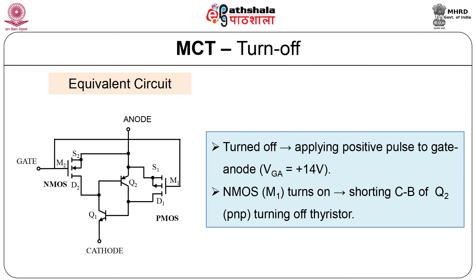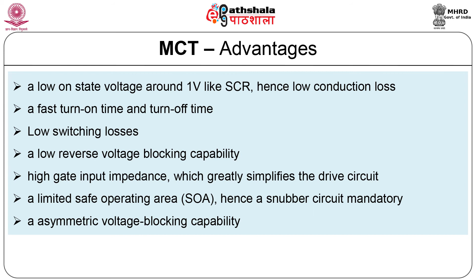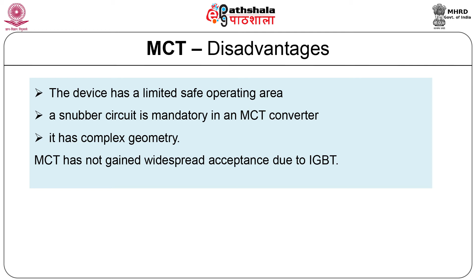The advantages of MCT are: low on-state voltage, fast turn on time, fast turn off time, low switching loss, and high gate input impedance. There are a few disadvantages: it has a limited safe operating area, a snubber circuit is mandatory in MCT converters, and most importantly, it has complex geometry, making fabrication difficult. MCT has not gained widespread acceptance due to IGBT, hence these are not widely used.